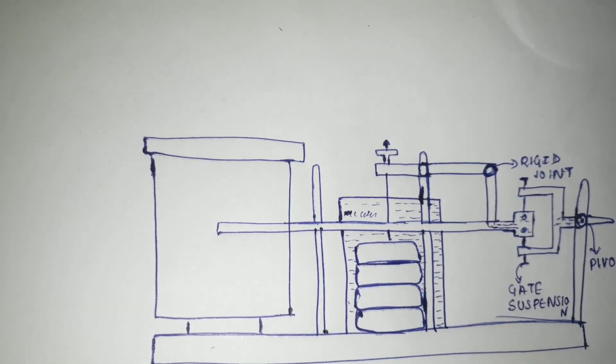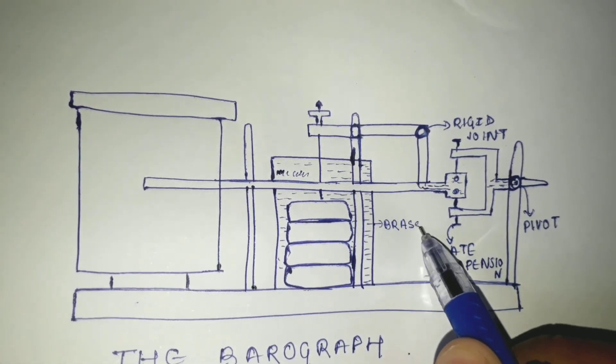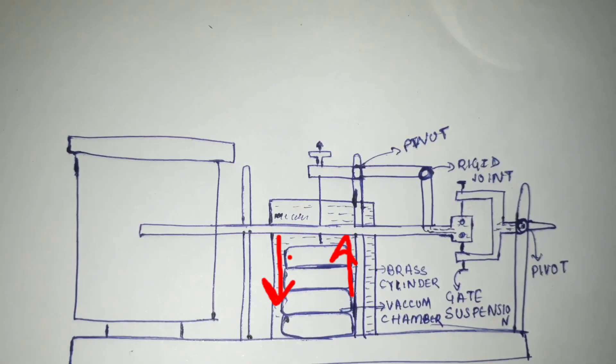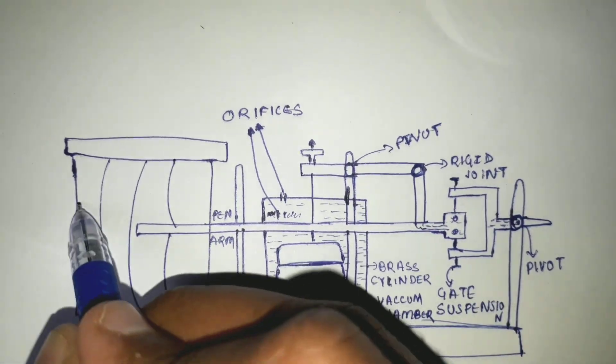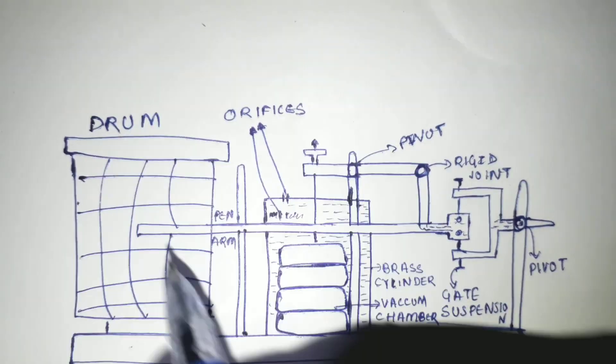So what is the purpose of this vacuum chamber? Whenever the atmospheric change occurs, this causes the top of the chamber to ascend or descend, and this movement is conveyed by a lever system to the stylus that moves up or down on the chart.